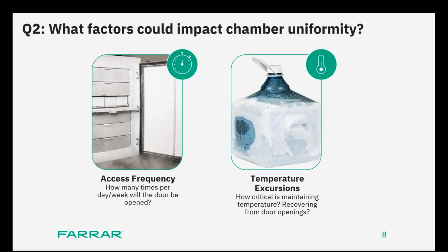That is it. So I'll give you an example in terms of high frequency and low frequency of door openings, right? So let's assume that you're working at a biorepository and you are getting 200,000 vials coming back from a very successful phase 3 clinical studies, and you need to store them at -80. Barring any recall from FDA for toxicity or any other adverse side effect, chances are these samples would be stored in a -80-degree chamber for 6 to 7 years until the company would come back and say, let's discard them, right? That's an ideal situation.